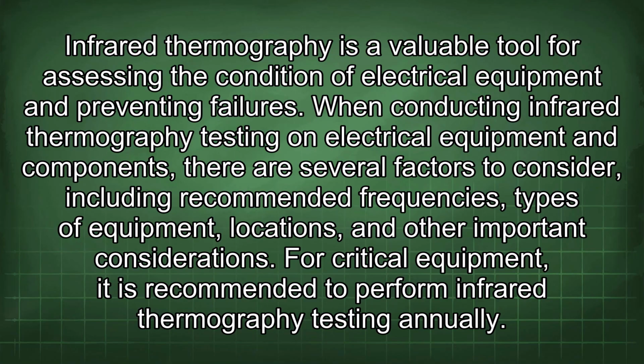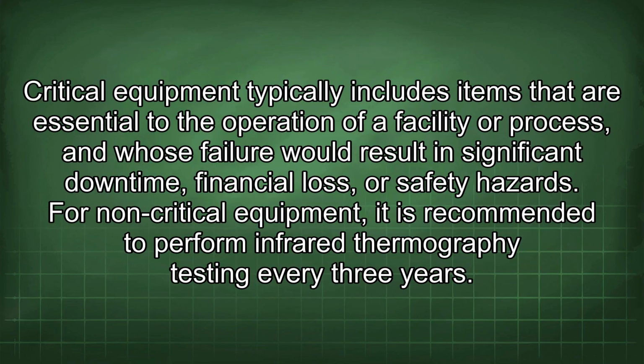Infrared thermography is a valuable tool for assessing the condition of electrical equipment and preventing failures. When conducting infrared thermography testing on electrical equipment and components, there are several factors to consider, including recommended frequencies, types of equipment, locations, and other important considerations. For critical equipment, it is recommended to perform infrared thermography testing annually. Critical equipment typically includes items that are essential to the operation of a facility or process, and whose failure would result in significant downtime, financial loss, or safety hazards.